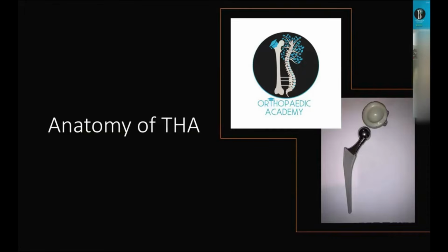On the interaction between the trunnion and the ball, that's again a friction, a torque surface due to the trunnion's differential shape. That can be based on the difference between the proximal end of the trunnion and the ratio to the distal end. That articulates on the inside, again with a friction fit, with the inside of the metal head, which is symmetrically shaped. And when we talk about interactions, we're talking about tribology.